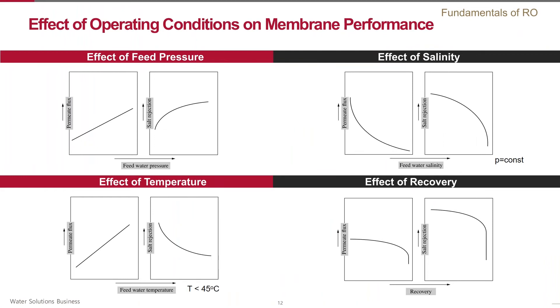For a system designer, it is very important to understand how major operating conditions such as feed salinity, temperature, pressure, and system recovery affect the membrane. Operating pressure directly affects water flux and indirectly affects salt rejection. Higher pressure results in higher flux. Salt transport is not directly affected by pressure, but because more water has passed through the membrane at higher pressure, the absolute salt concentration in the permeate is lower — so it appears as if salt passage decreases and salt rejection increases as pressure increases.